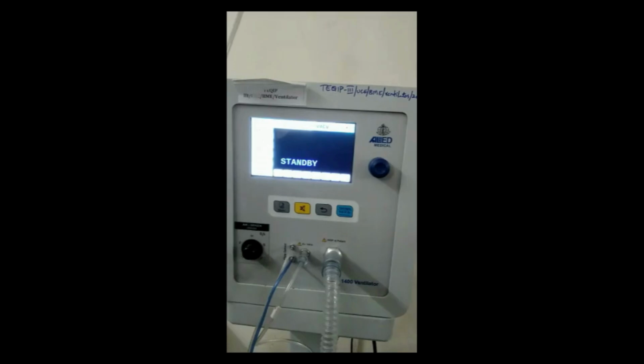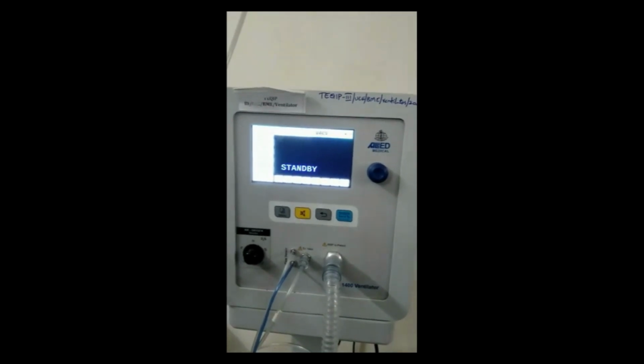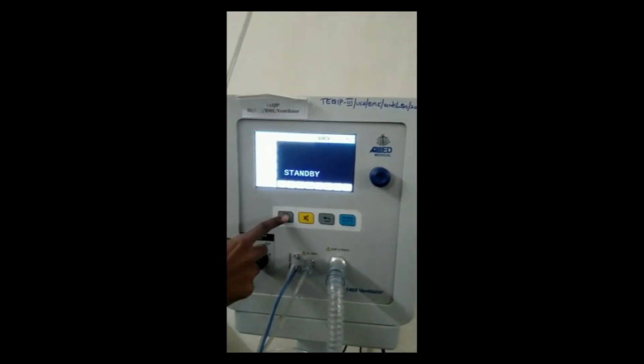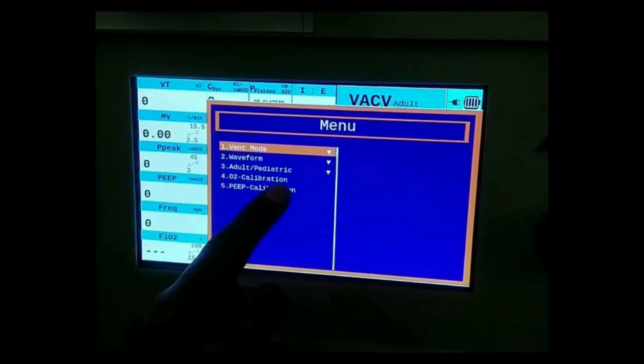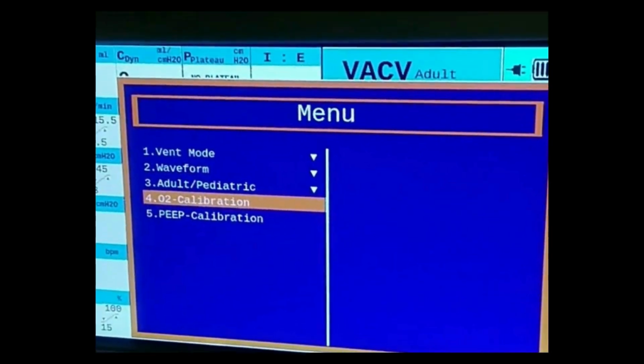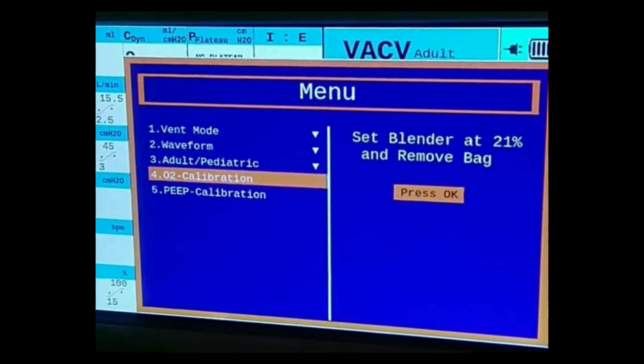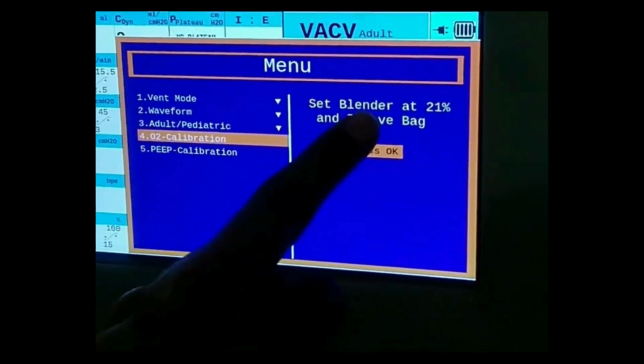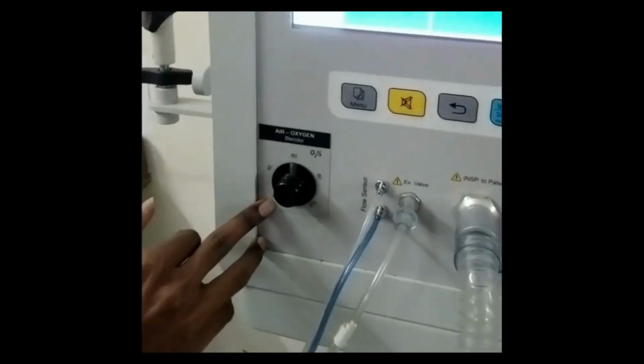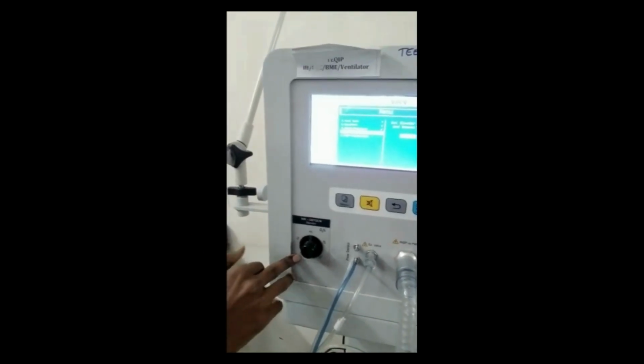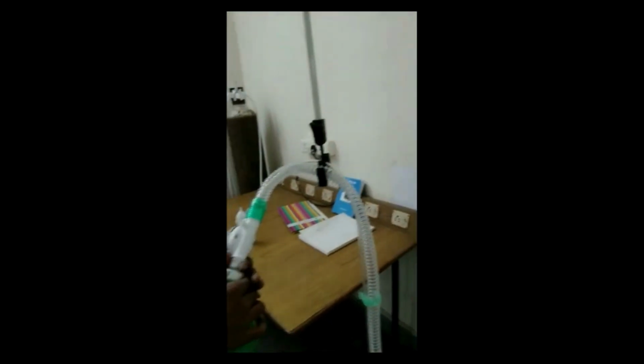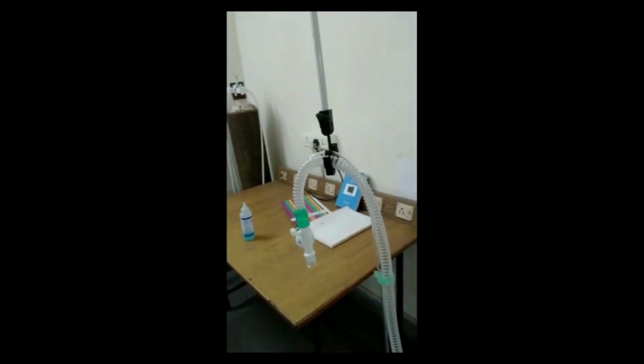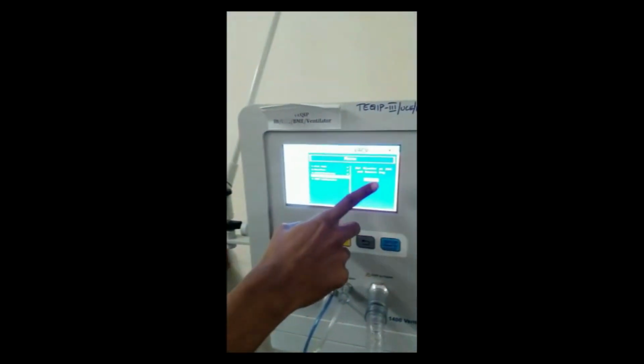Now we will do the O2 calibration of this ventilator. So we will simply press this menu button, and we can see the options, and we can go to calibration by simply clicking this knob. It is saying to set the blender at 21% and remove the bag. As you can see, it is already set to 21%. So here we will remove the bag first. As I remove the bag, we can simply press the OK button here.